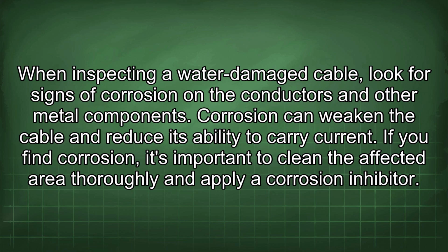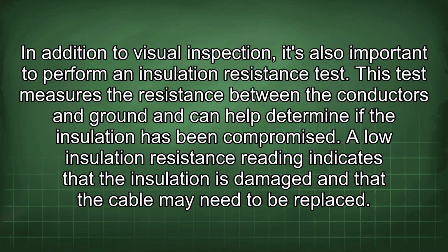If you find corrosion, it's important to clean the affected area thoroughly and apply a corrosion inhibitor. In addition to visual inspection, it's also important to perform an insulation resistance test. This test measures the resistance between the conductors and ground and can help determine if the insulation has been compromised. A low insulation resistance reading indicates that the insulation is damaged and that the cable may need to be replaced.